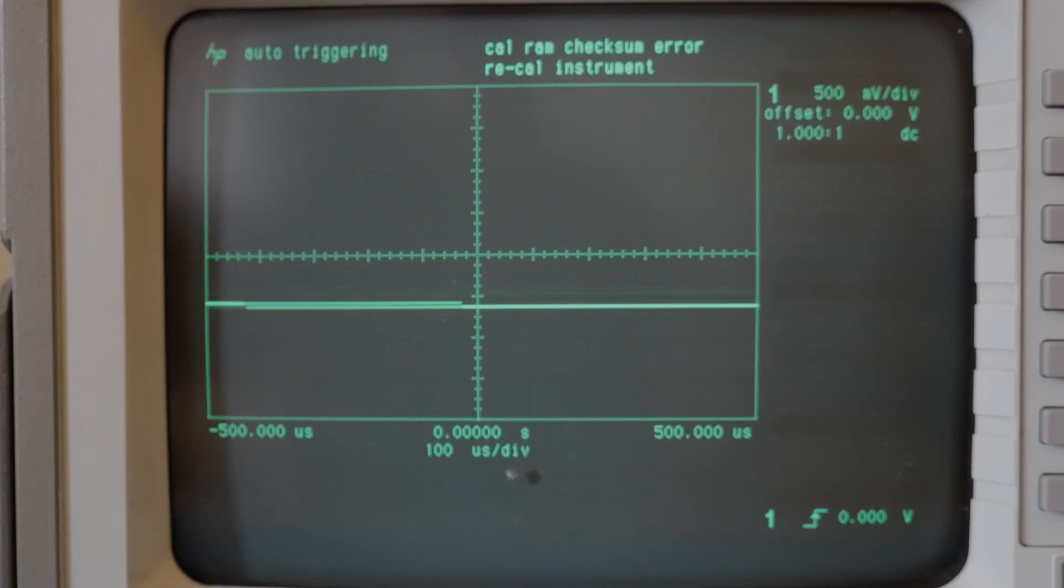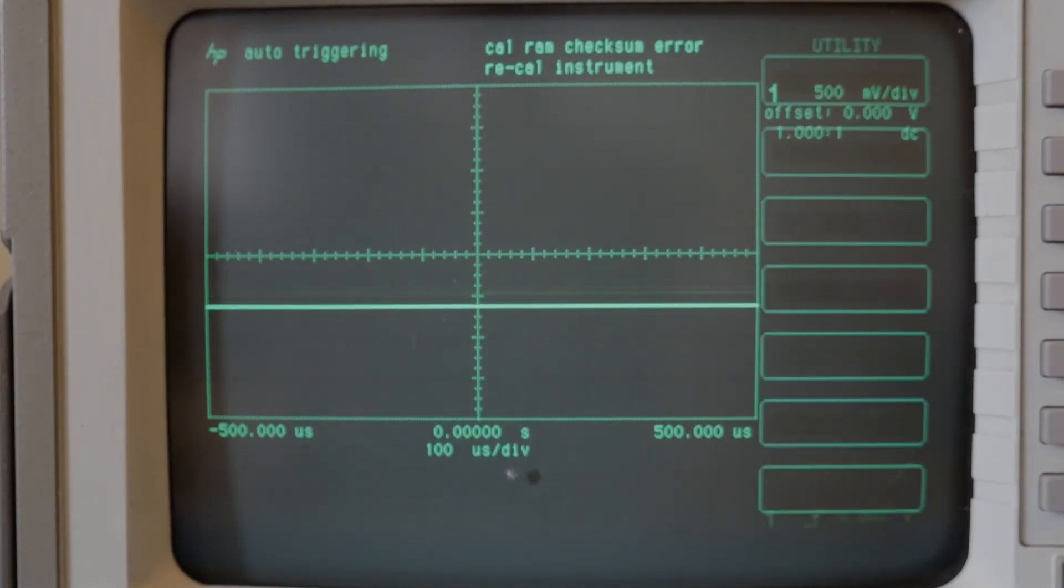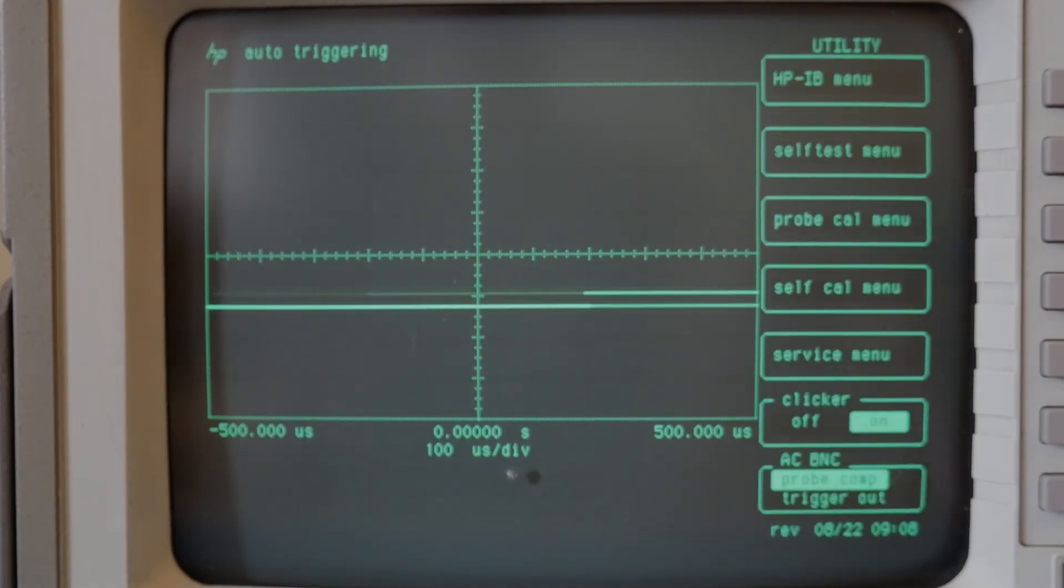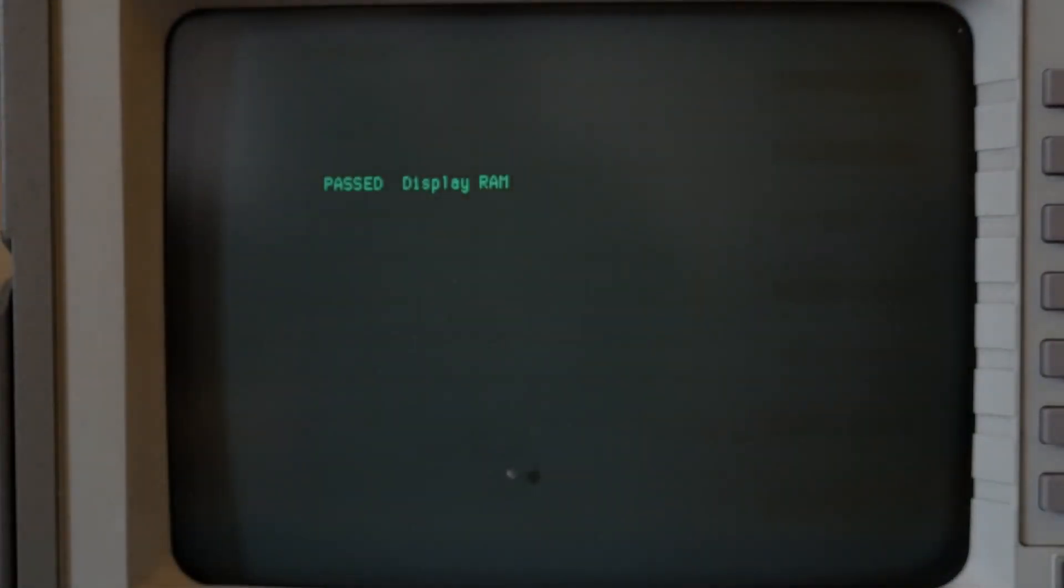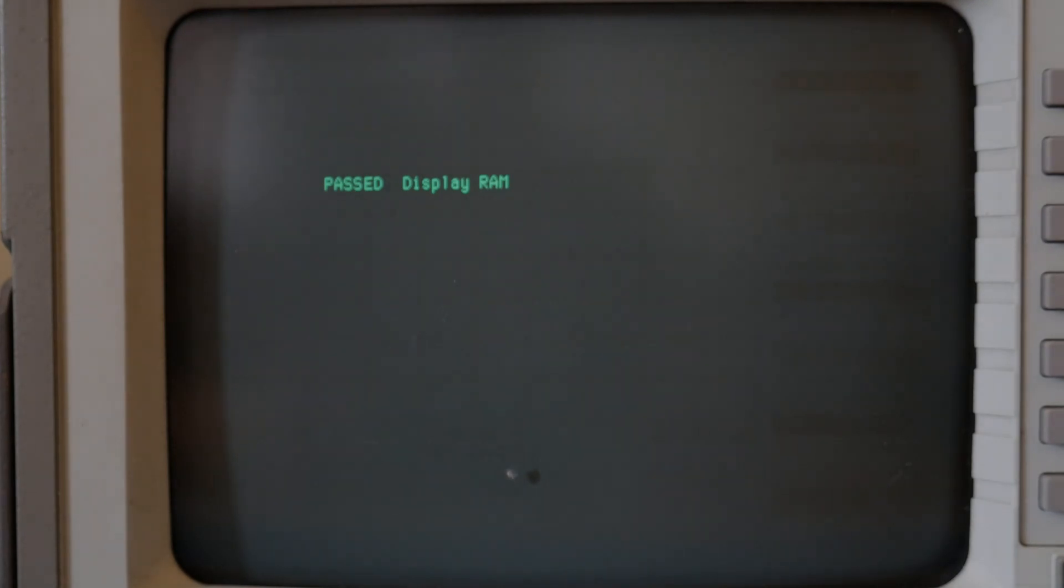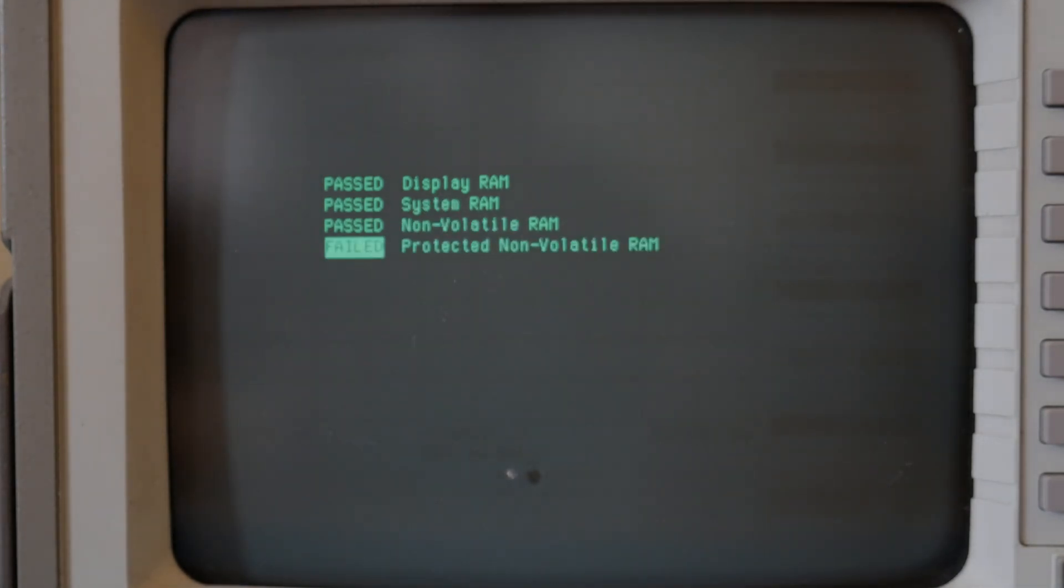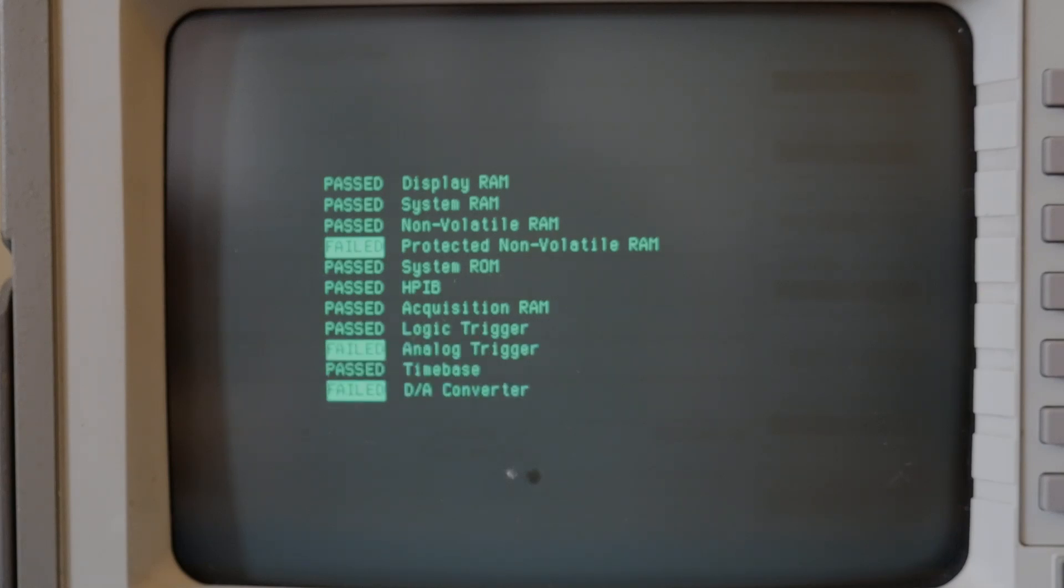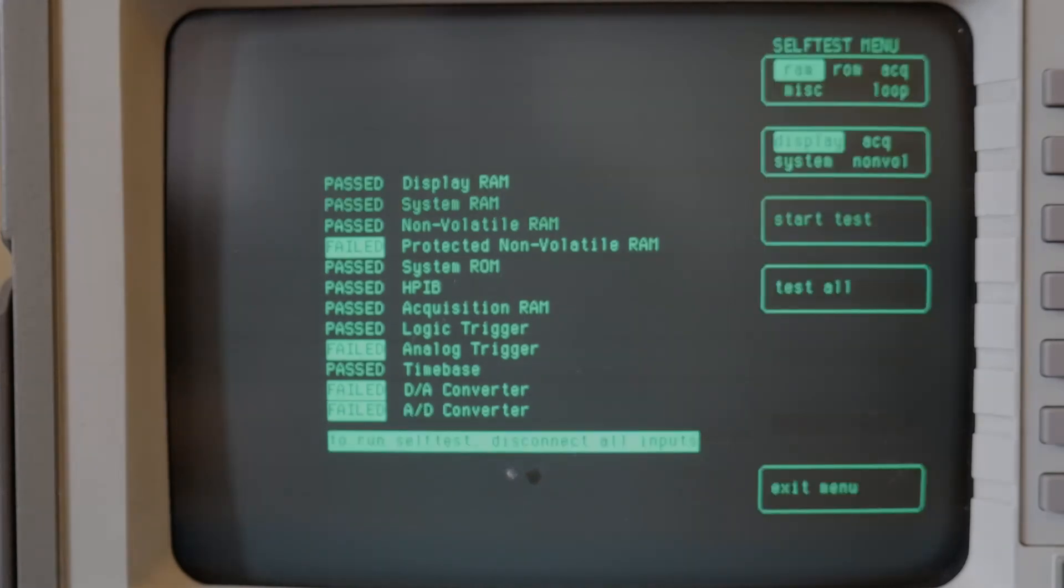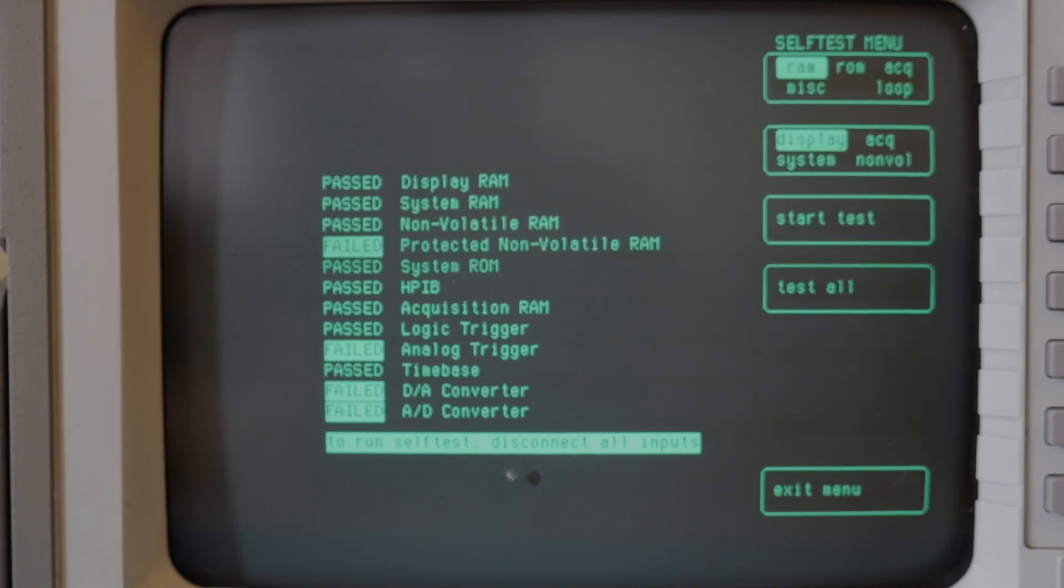Okay let's run the self test on this and see what we get. Press the utility button here and the self test menu and say test all. Okay so it passed the display RAM test. Oh it failed the protected non-volatile RAM. Failed the analog trigger and failed the D to A converter and it failed the A to D converter at the end. So we've got some issues.